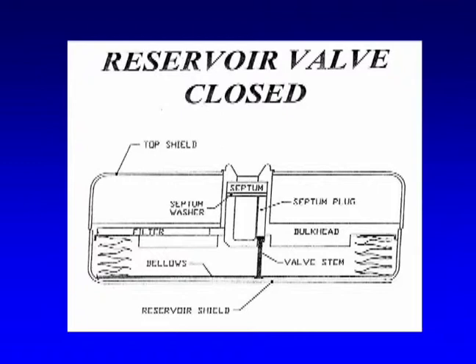However, these valve stems have sometimes gotten stuck, and Medtronic has provided elaborate protocols for clinicians who suspect a stuck valve stem. If you fill the reservoir, hit resistance, and the stem gets stuck, you may end up with a stuck open reservoir system that could affect drug delivery.